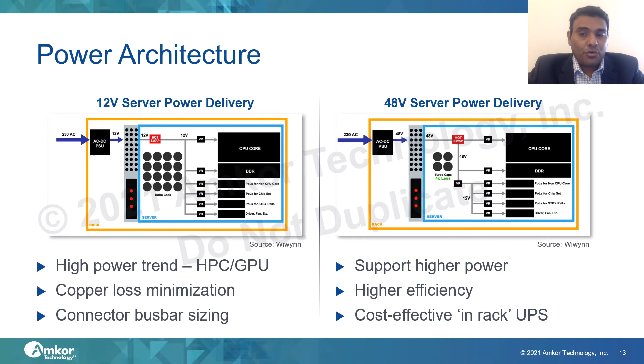Server boards are also becoming denser to accommodate higher functionality. For example, Intel's data center chip roadmap suggests its current chip generation VR13 is at 400 watt instantaneous peak power, while the next generation VR13.HC is going to be at 800 watt, and the VR14 version is planned to be at around a kilowatt. This is shifting power architectures to either a traditional two-stage approach using a transformer, or a direct approach from AC to 400 to 48 volt.